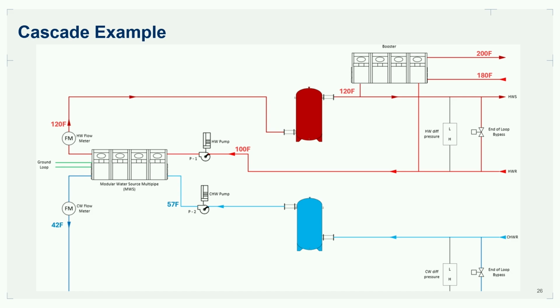Or maybe we should be doing a low temp unit that is getting us 120 out of the condenser side and chilled water back to the cooling loop or to the well field, right? Let's shift those BTUs internally where we can. Crank that outside air damper down to its minimum position, reintroduce those BTUs. You know, the days of airside economizer in upstate New York, like we want that cooling. We need to keep those in our buildings. So let's reintroduce those cooling loads, handle that with our low temp unit, and then boost it up from there to get up to our 200 degrees in this example.